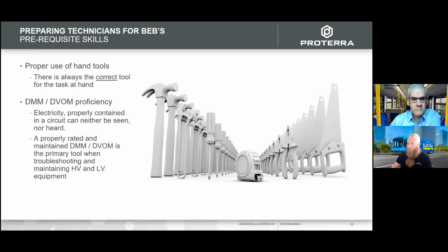Know how to inspect your leads and confirm they're also rated for the task at hand. Just as importantly, we need to know how to use our leads properly—don't pierce through the insulation, understand how to actually back probe and when it's appropriate to do so without causing damage to the circuit. Be it high voltage or low voltage, there's always the inherent risk that if you back probe incorrectly, you can cause more work for yourself in the long run.